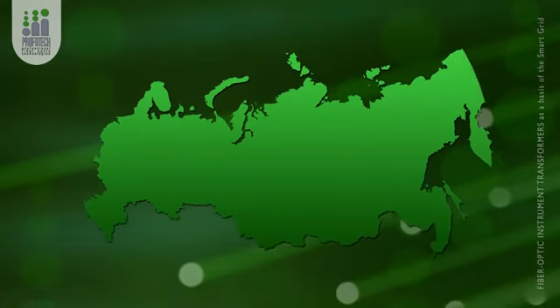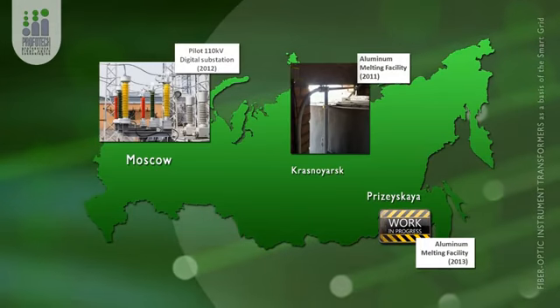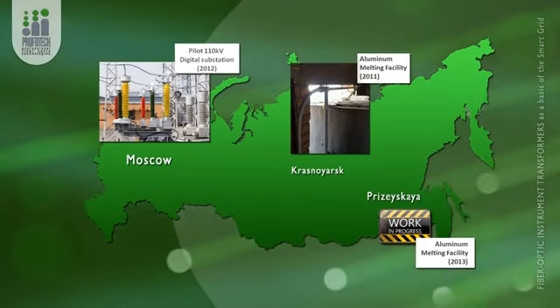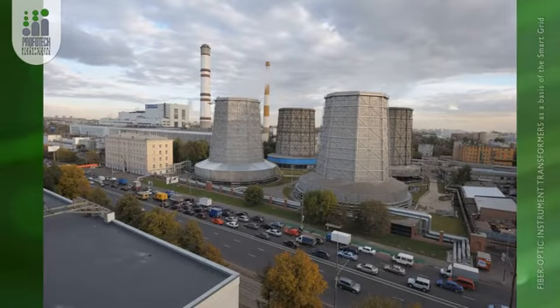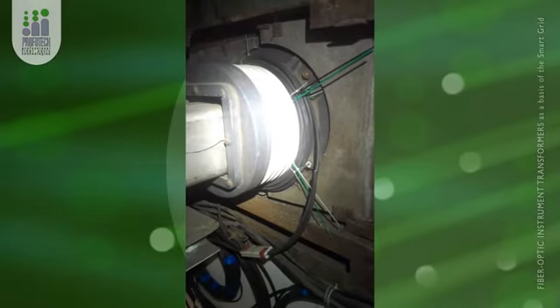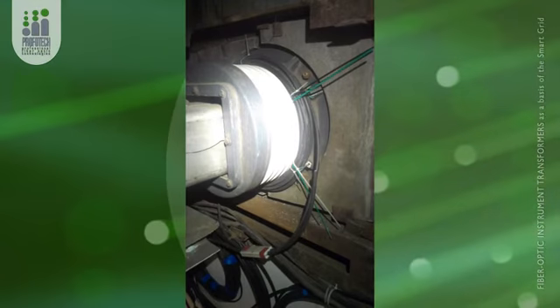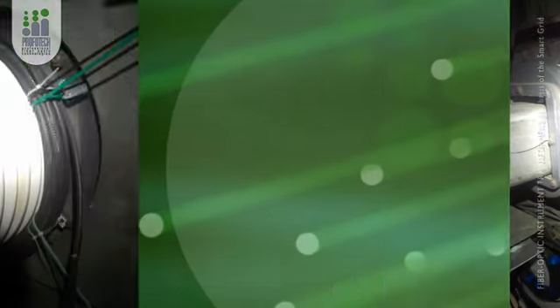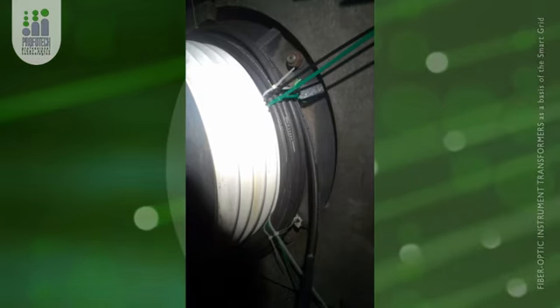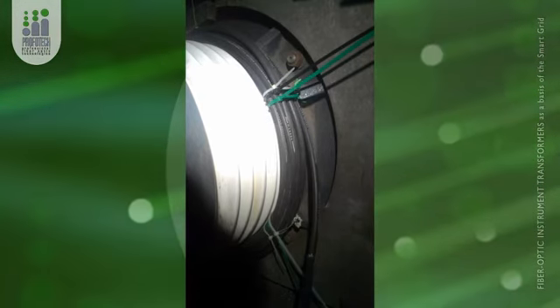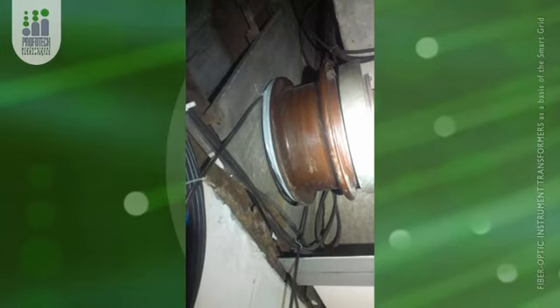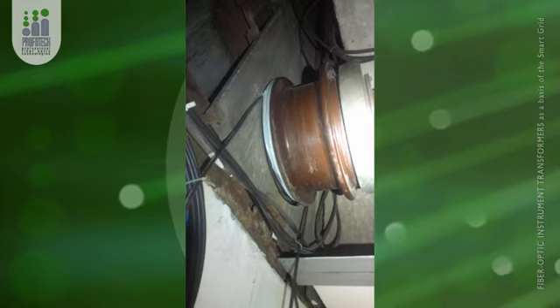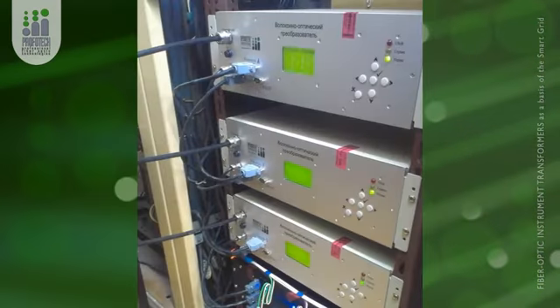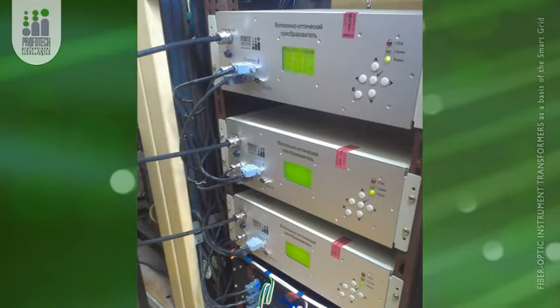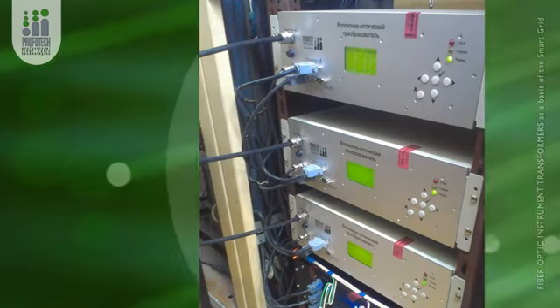Project number 3 is the steam power plant installation in Moscow, where we use the open-loop current sensor. It was actually wound around the current carrying bus without the need to dismount the bus. This is really good for real case installations, as you are not required to dismantle anything. Just install it without the need to stop any equipment for a long period of time. Simply wind the fiber optic cable around the current carrying bus. This is used for both revenue metering and for accuracy testing of the installed instrument transformers, like second reference instrument transformers.